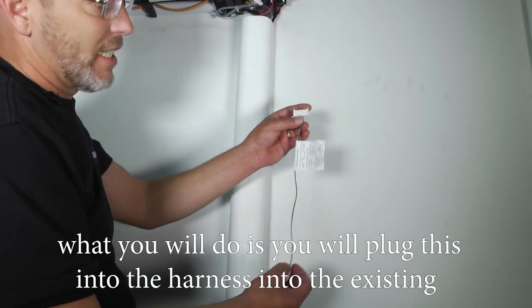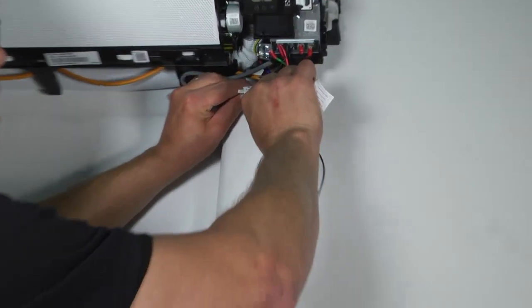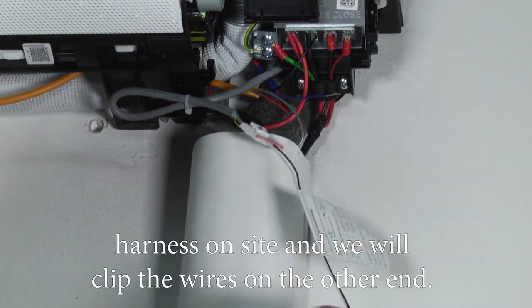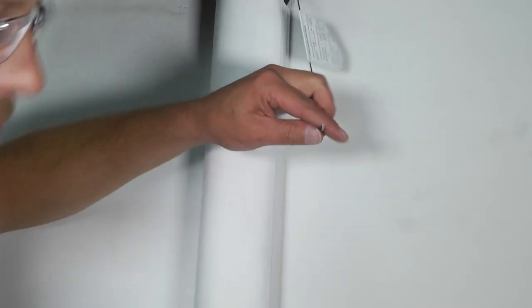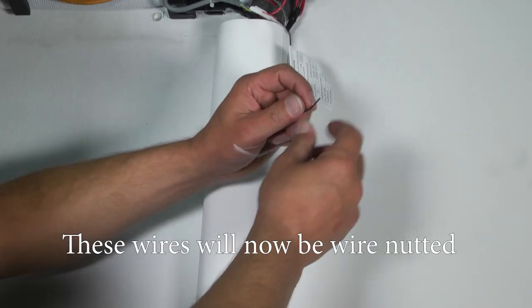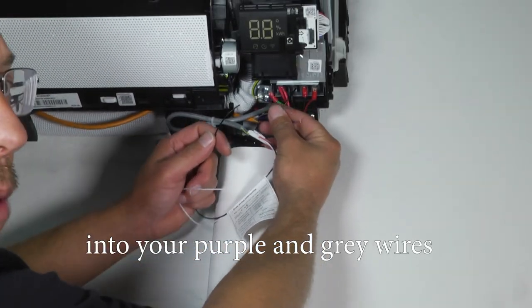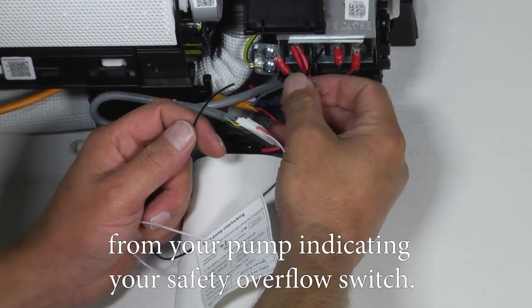what you'll do is you'll plug this into the harness, into the existing harness on site, and we'll clip the wires on the other end. These wires will now be wire nutted into your purple and gray wires from your pump, indicating your safety overflow switch.